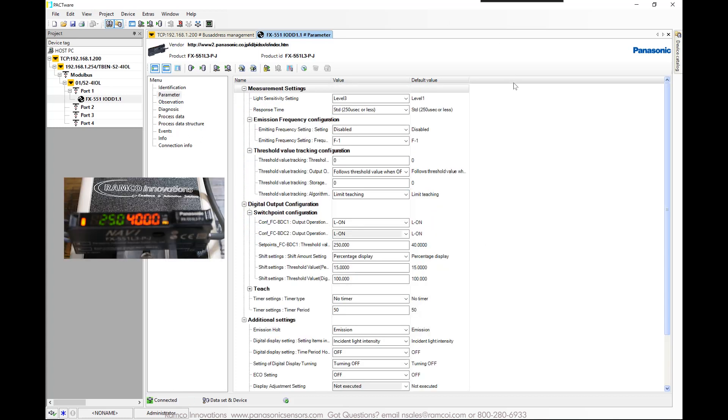Notice the fiber amplifier. The existing threshold value is set for 250. However, when no part is present, the incident light level never goes below 448, so the output always stays on.